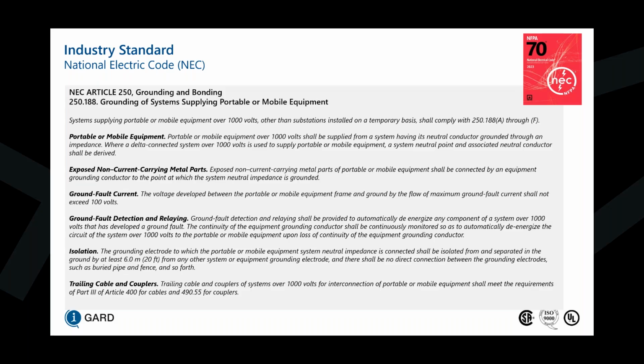In terms of isolation, the grounding electrode to which the portable or mobile equipment system neutral impedance is connected shall be isolated from and separated in the ground by at least 6 meters from any other system or equipment grounding electrode, and there shall be no direct connection between the grounding electrodes, such as buried pipe and fence, and so forth. For trailing cable, it has to meet the requirements of Part 3 of Article 400 for cables and 490.55 for couplers.